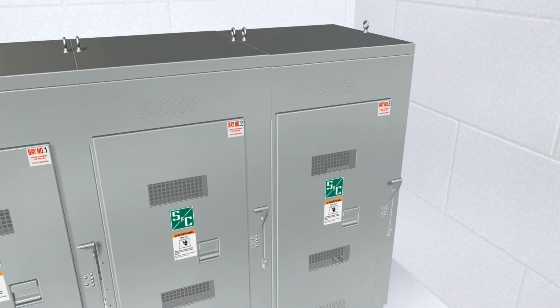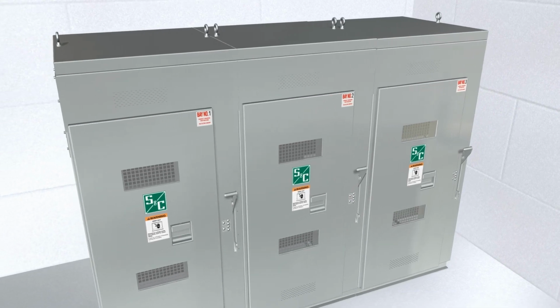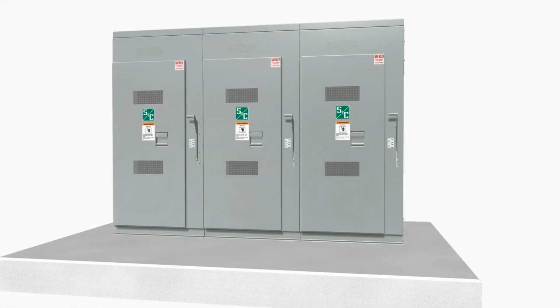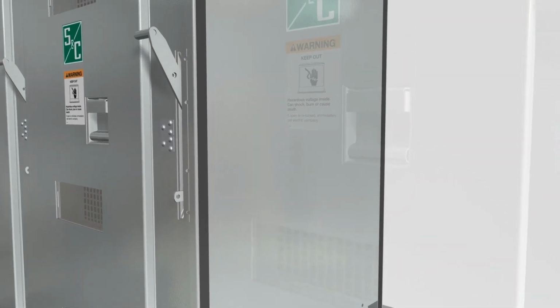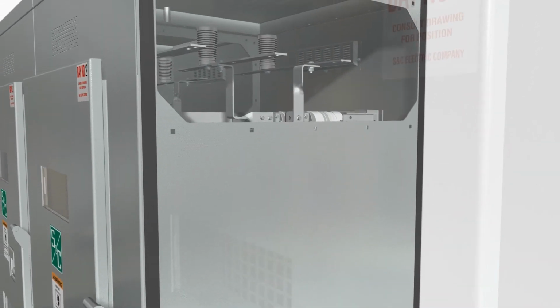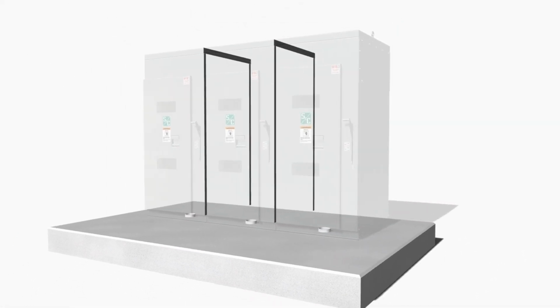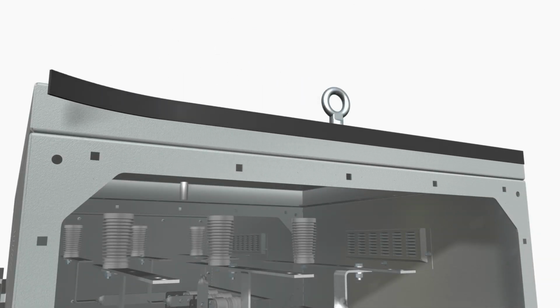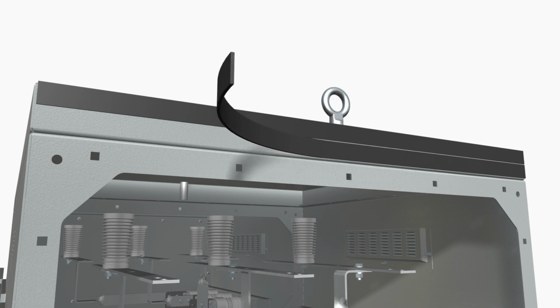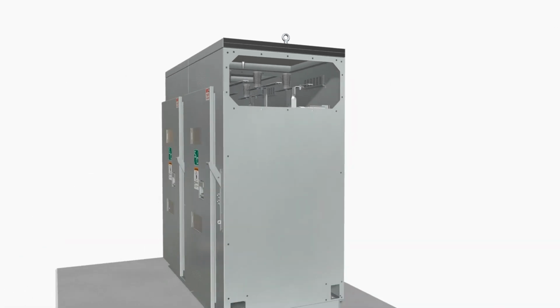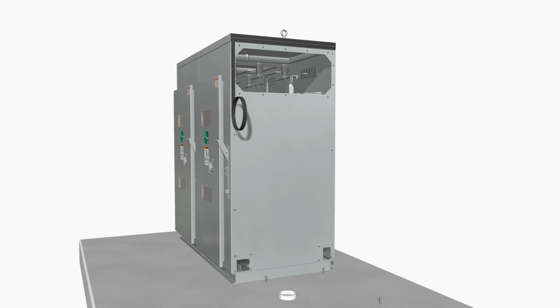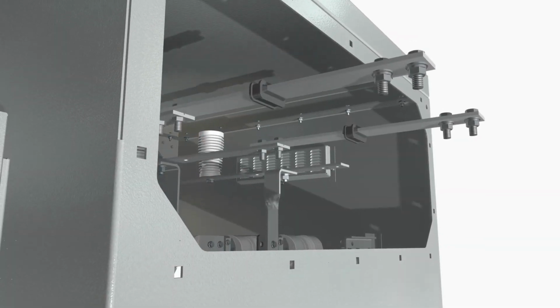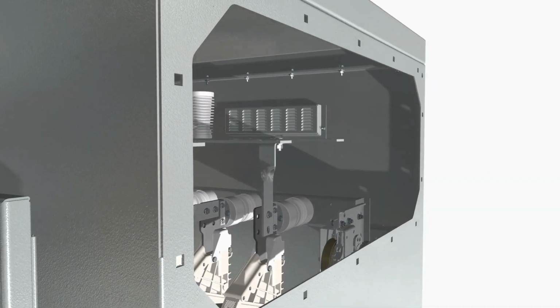Step 4. On indoor assemblies furnished with drip-proof or dust-proof construction and on outdoor multi-bay assemblies, obtain a weather-tight seal between units by applying the provided adhesive-backed foam gasket tape around exposed edges and roof section between adjoining units. On outdoor switchgear, 2 strips of gasket tape are used at the top of the enclosure. Strips of gasket tape at the top of the roof section should be installed the full depth of the enclosure, with strips at side edges starting below the top strips. Remove any bus opening support straps before applying the gasket.